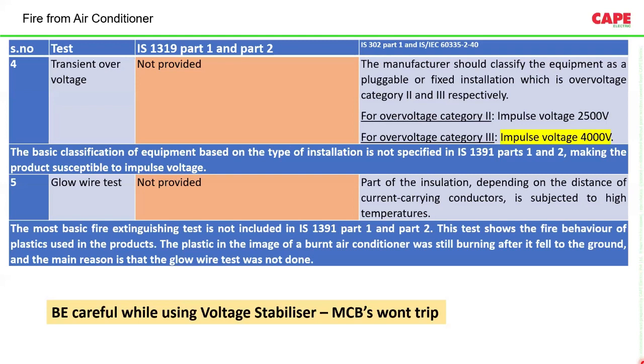Of course, overload protection is possible, but instantaneous tripping may not be possible because voltage stabilizers are adding impedance in the circuit. As a result, the fault current of negligible impedance, or short circuit current, is reduced and the disconnection time will be higher, resulting in a fire. You have to be very careful.